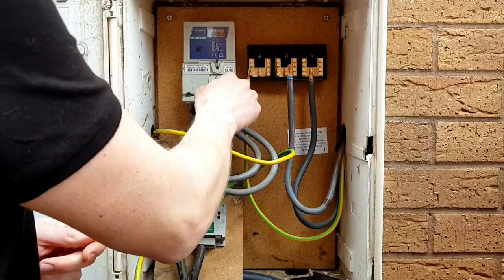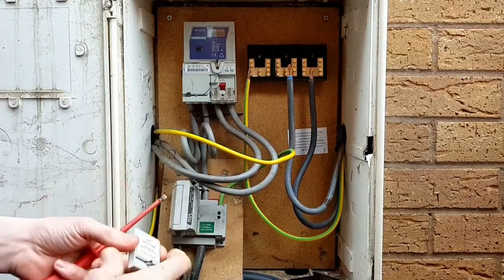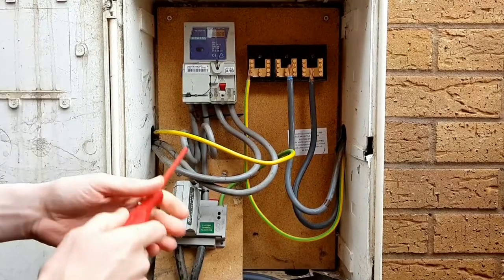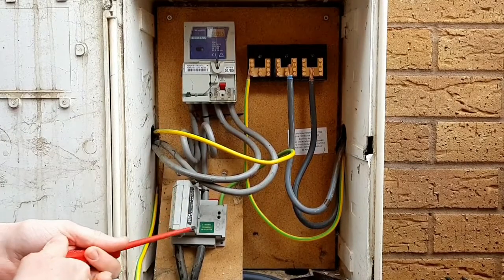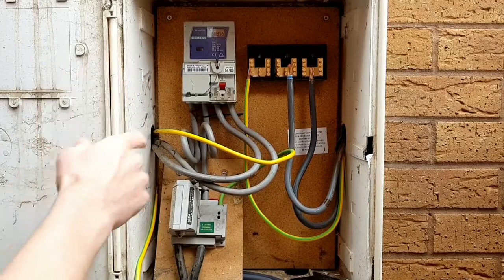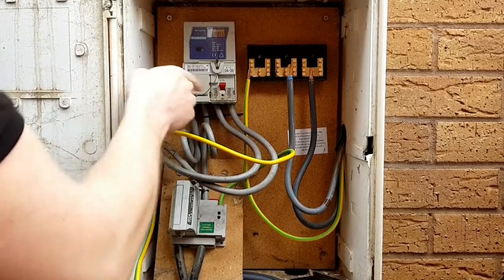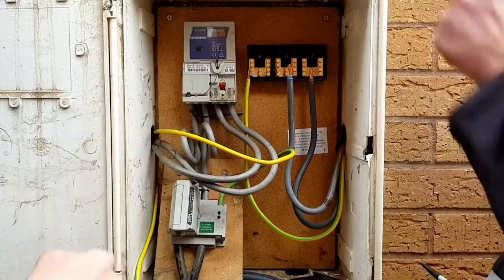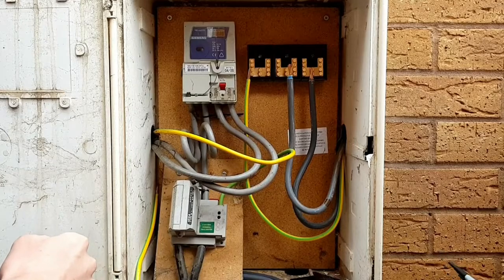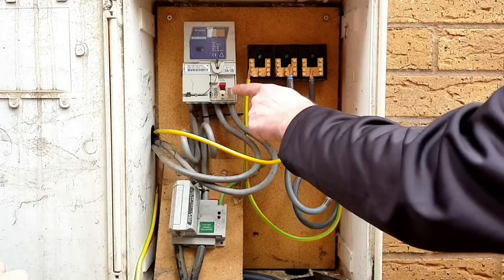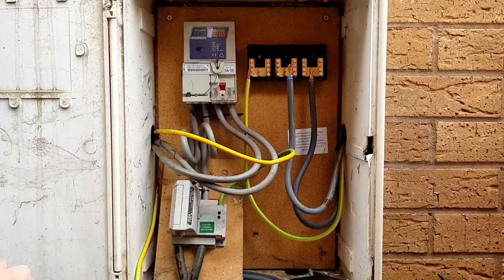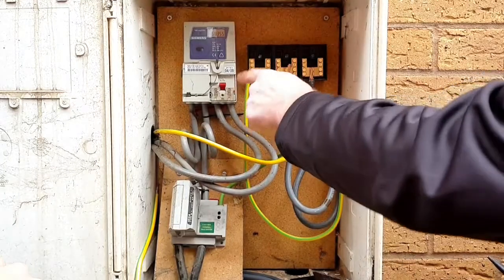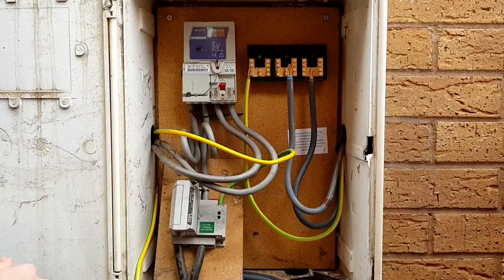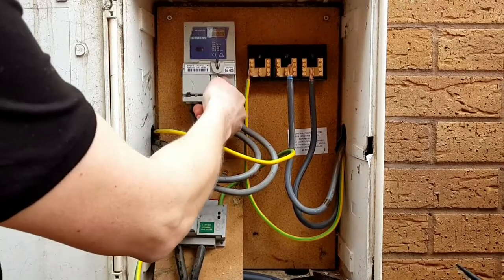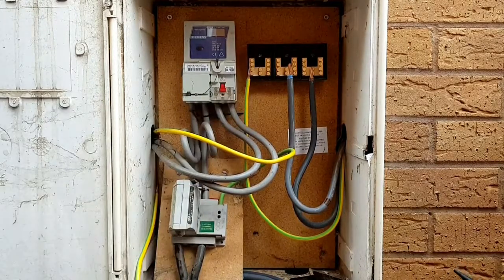And it also should have a little plastic cover over the live terminals there, which means that we can't get a shock from that. So we're ready to turn this off. We'll remove the little plastic protective cover that's in place there, and then we can carry out the safe isolation procedure. Yeah, just one word of warning. Remember, because we're operating this switch, that we've de-energized the circuits within the actual installation, so we're not turning this off on full load current. That wouldn't be good practice. So without further ado, we'll turn the power off. So there we go, that's now isolated.